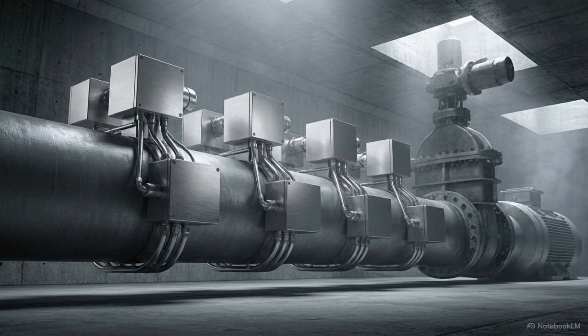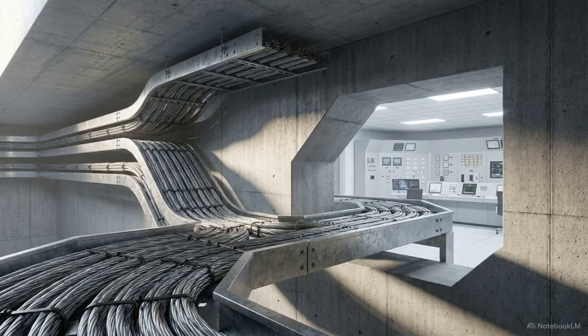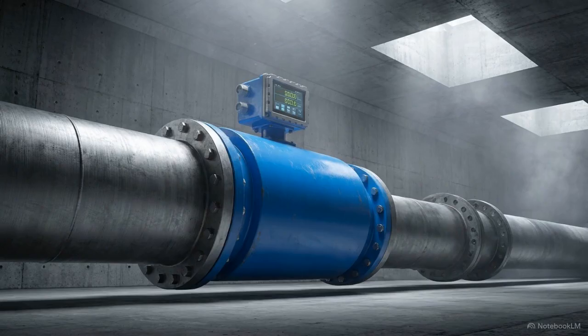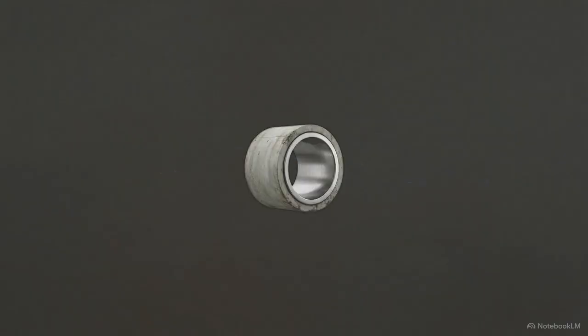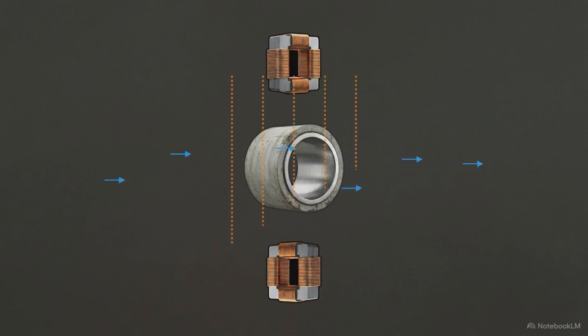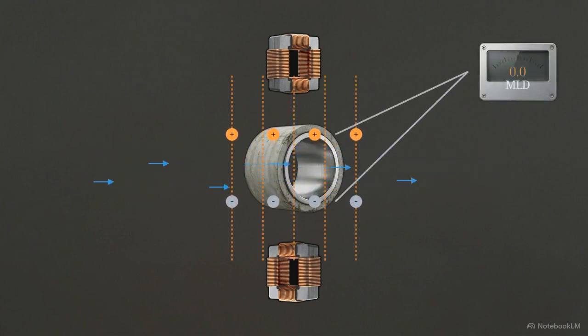During continuous 20 MLD operation, physical conditions inside the pipes are constantly measured by field instruments and transmitted via 4 to 20 milliamp signals along armored cables back to the SCADA control room. Volumetric output is tracked by a 600mm electromagnetic flow meter. Utilizing Faraday's law of induction, it passes a magnetic field through the conductive river water, allowing the system to calculate precise flow rates based on the voltage generated by the moving fluid.